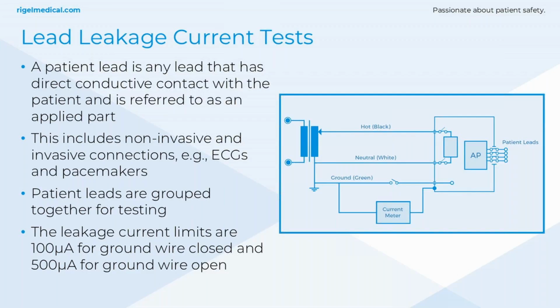And you can activate that using the ground switch on the device, as we did with the touch leakage. And the SafeTest 60 Plus has those test limits built in. So when you open the ground, it will be set to a 500 microamp limit, and when you introduce the ground wire closed, it will be 100 microamps, and I'll show you that in the next video.